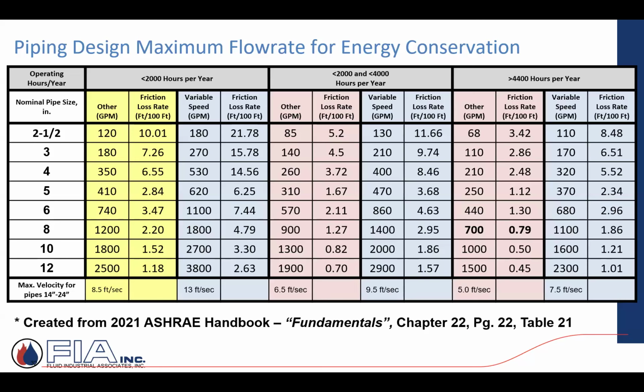These are some charts out of an ASHRAE book, a 2021 Fundamentals book, and it talks about different diameter pipes. They have it in categories. How many hours out of the year is that pump running? The longer it runs, the lower the flow rate that they want to select for energy consumption. They're a little more liberal on the lesser hours per year. But again, it's all referencing, what's that pressure drop? And you'll see it, feet per 100 feet, feet per 100 feet, etc. So it's just kind of an industry standard. When you calculate that pressure drop, that answer you come up with is usually feet per 100 feet. And then you're just going to say, okay, how many feet do I have?